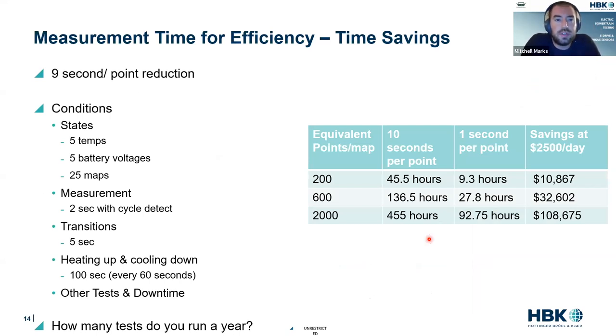But what's the real problem with efficiency mapping? Why does it take so long? What we find is that people doing these efficiency maps will do them at a variety of temperatures. Let's say you're doing 5 temperatures, because these machines and inverters get hot, and their efficiency changes with temperature. These inverters and motors also perform differently as the battery voltage depletes. Maybe at 100% we're at 400 volts, but at 50% we're at 350 volts, and we want to characterize these different battery voltages. So now we have this combination of temperature and voltage. One efficiency map might end up being 25 maps to really understand the system.